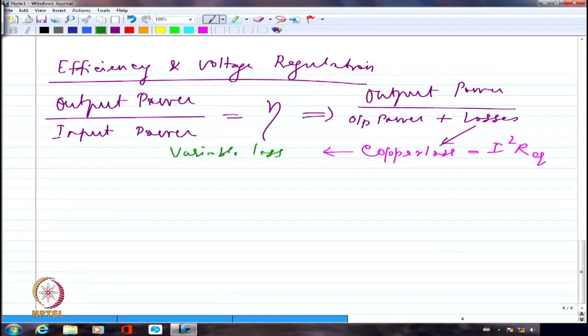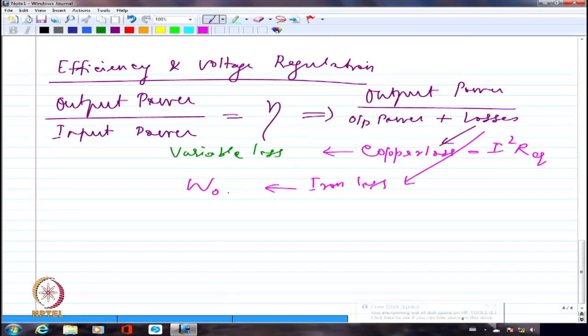The second kind of loss I have is iron loss or constant loss, which we already saw corresponds to IC square RC. If I say it in terms of the equivalent circuit, this will be equal to hysteresis loss plus eddy current loss, or I can also say this is W naught, what I got in the no load test. When I did the no load test, I got some W naught. I applied rated voltage at rated frequency, so hopefully the flux is at rated value. If the flux is at rated value, whatever loss I get is the iron loss. So this is actually the constant loss.